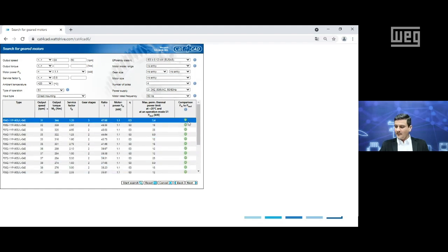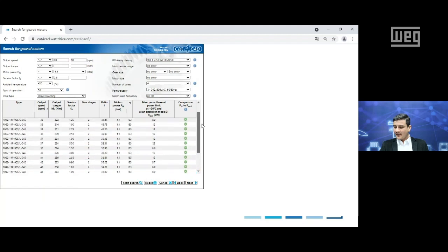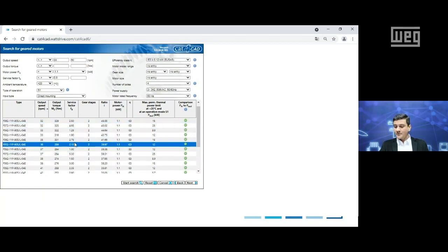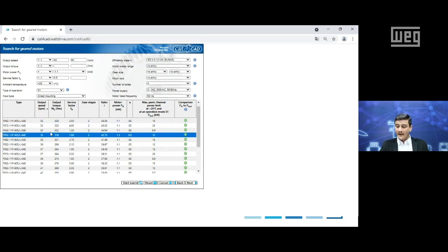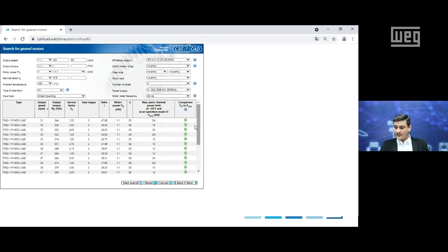So as you can see here, the Cat4CAD tool gave us a lot of options, a lot of combinations. You can see here the output speed that we informed from the beginning. But one of the most important points that you need to observe for choosing the geared solution is the service factor of the gear. So you will understand that depending on the service factor, this will be applicable for different applications. In this case, we are going to consider a service factor of 1.2, which means light loads, okay? So we are going to select this field.